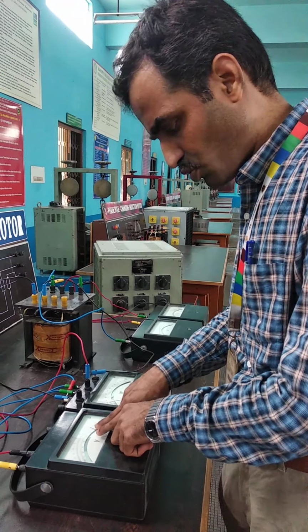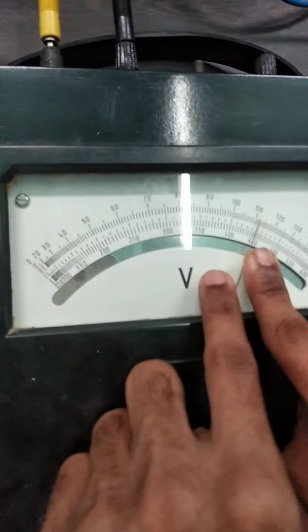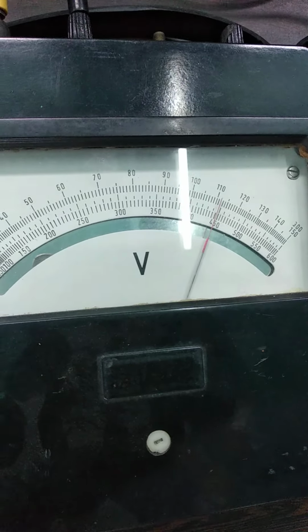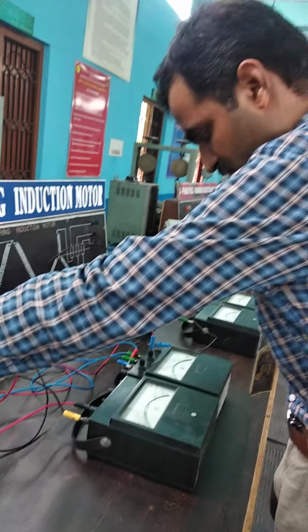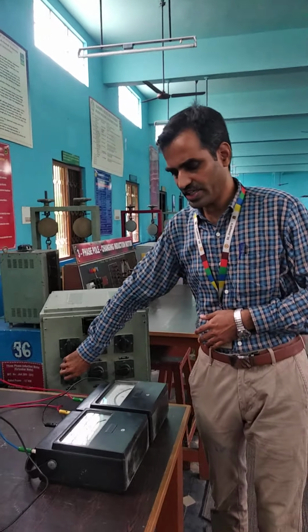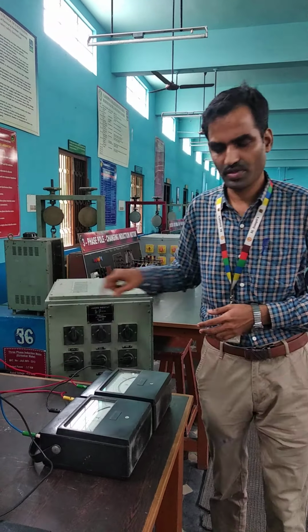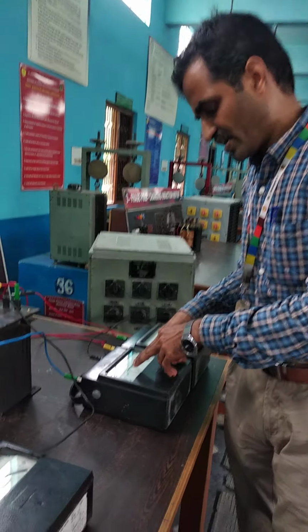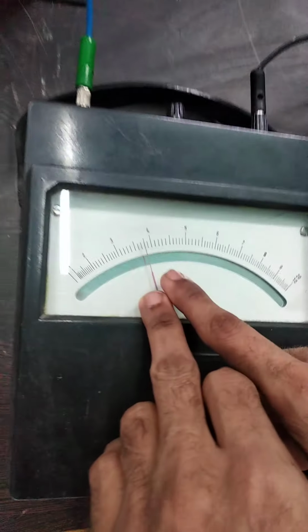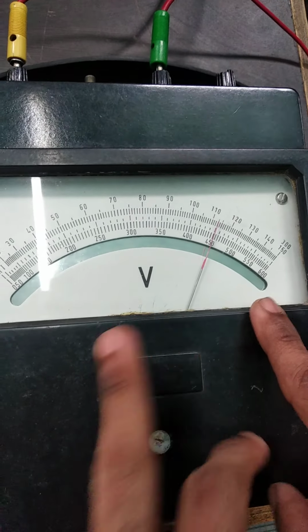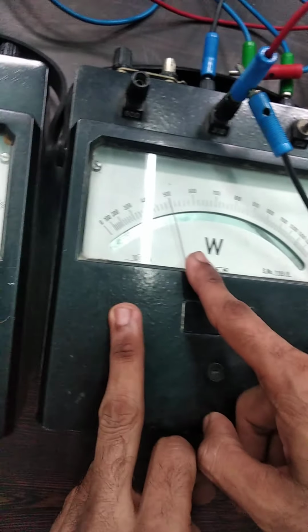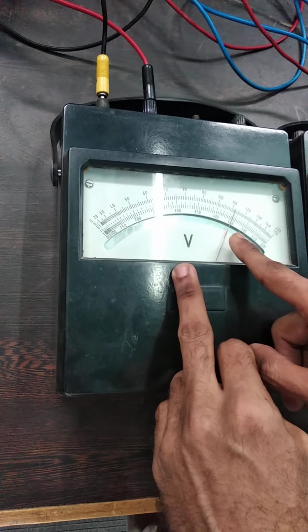And then you can see the voltage has gone down. Okay, so before switching on the next load, again I vary the auto transformer to bring to original 115 volt. Then I switch on the next load. Okay, so here you can see the load current has increased further and the load voltage has decreased further, and the power on the primary side is increased and the voltage on the primary side has reduced.